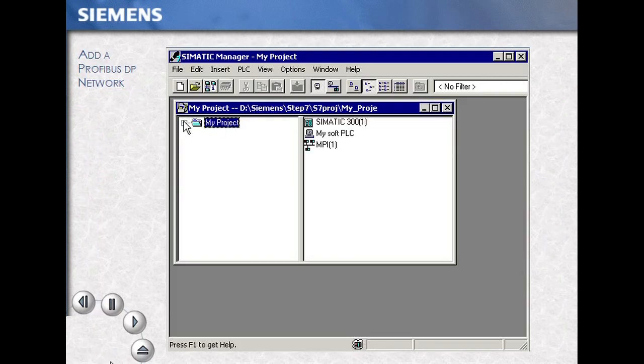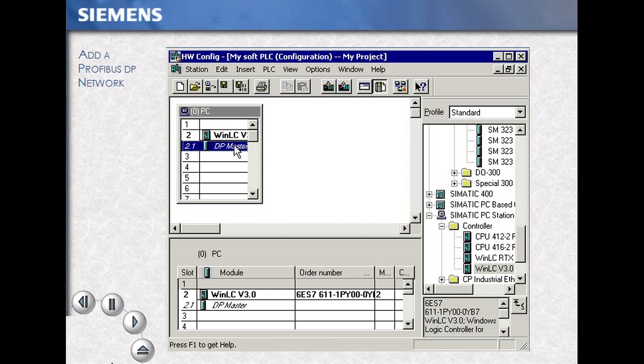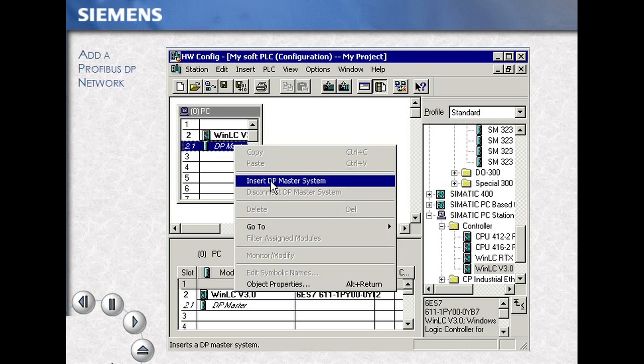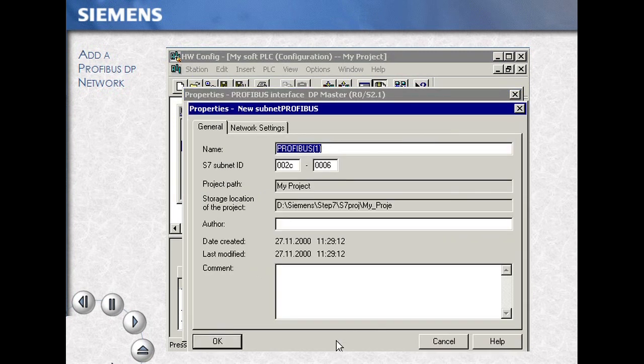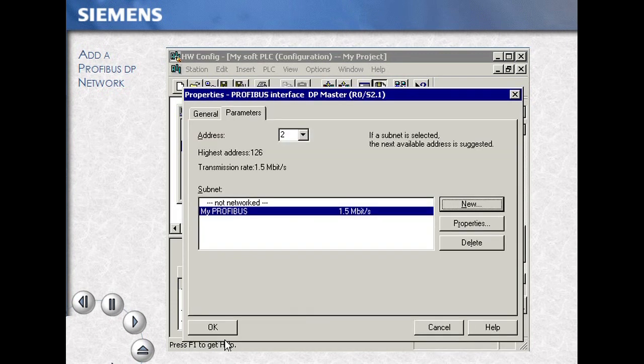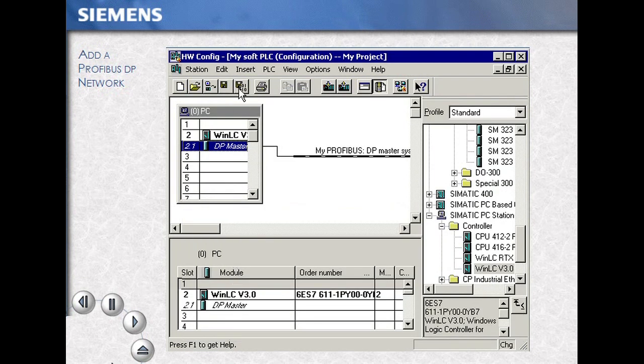Open your project and select your station, then double-click on the configuration. Select your DP Master System, right mouse click, Insert DP Master System. Select New to begin a new network. Type in the name of your network — in this case, MyProfibus. OK your selection and confirm with OK. Then save and compile your work.